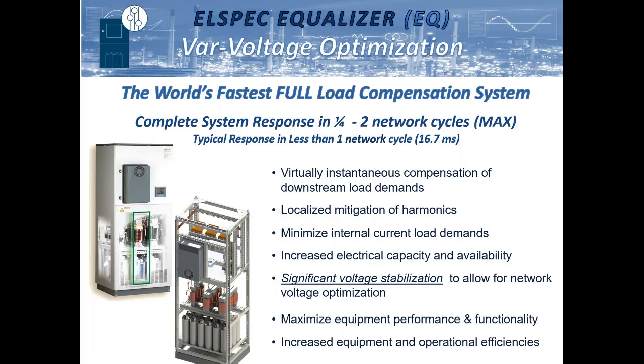All of our systems are fully electronically switched, so we don't utilize electrical contactors. We measure and calculate the network load demand in less than a quarter of a network cycle. And then the system actually waits for the voltage waveform on each phase to cross the zero threshold. And at that point, you bring in each of those phases. So in doing so, we're able to have total response time and bring in as many groups as necessary in typically less than one network cycle, and we can bring it all out in less than one network cycle.